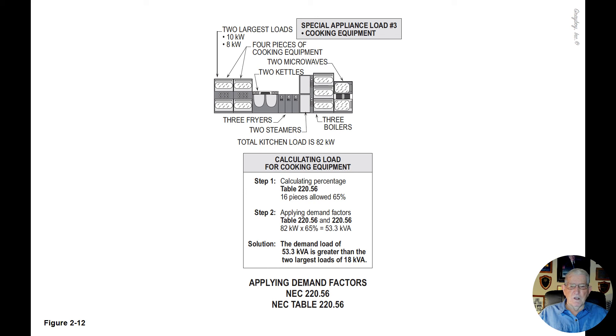53.3 kVA is greater than the two largest loads of 18 kW, seen at the top left of the illustrated cooking equipment. The two largest loads — 10 kW and 8 kW — is where the 18 kW figure comes from. All we're doing is converting kW to kVA, as the code requires.